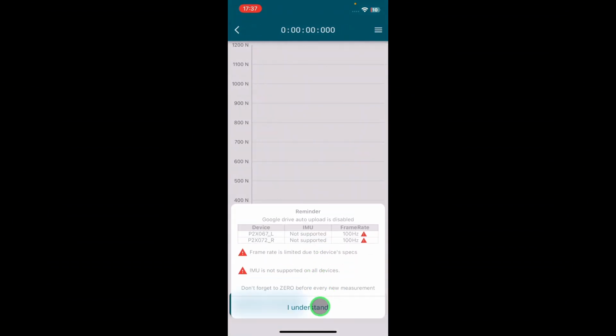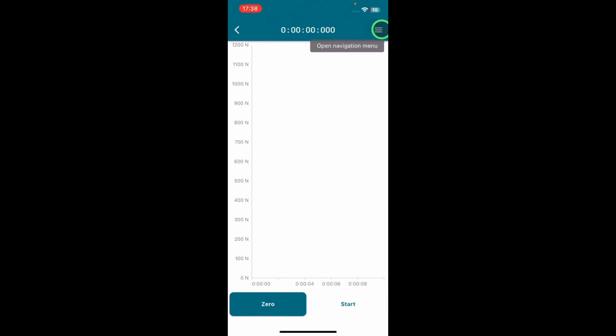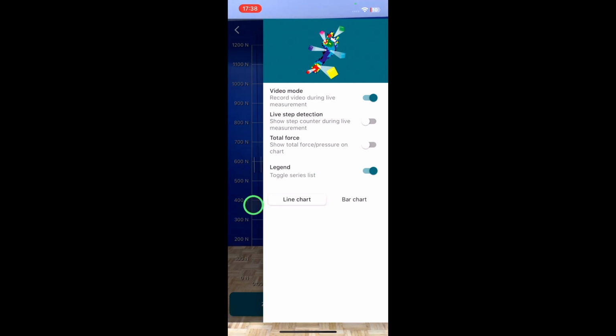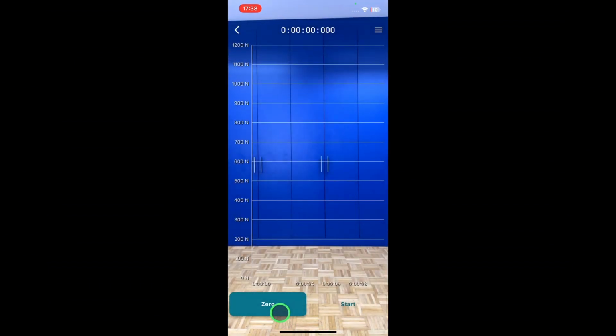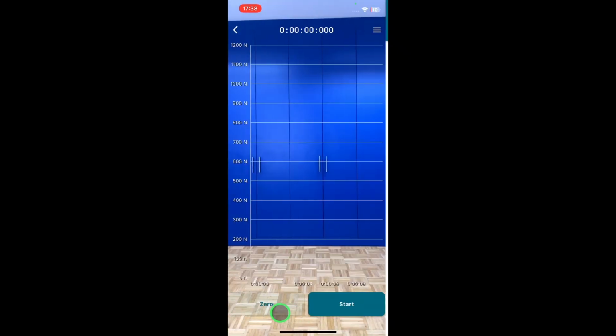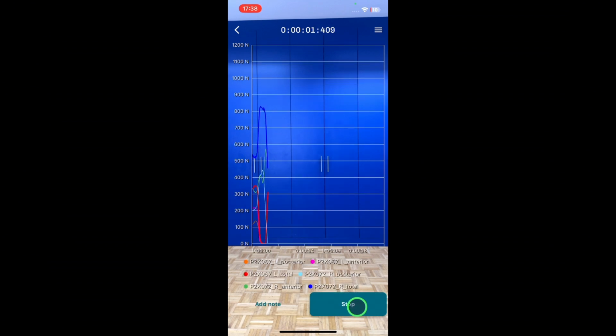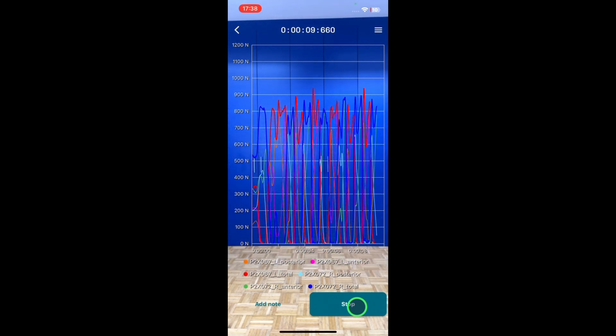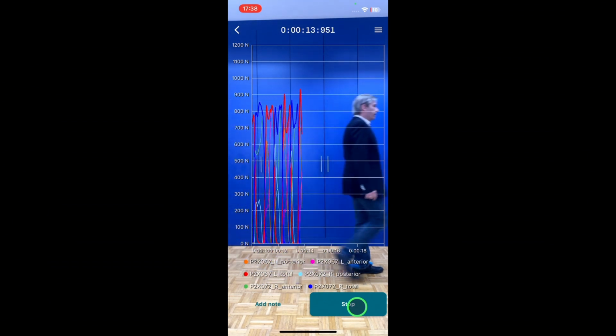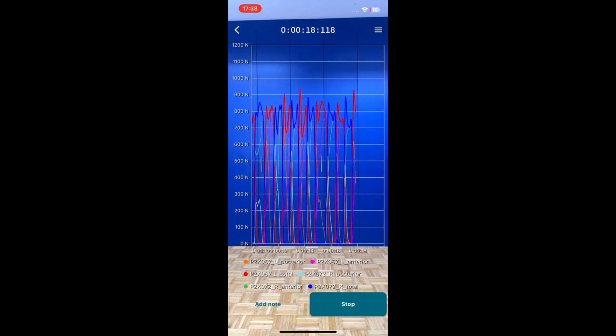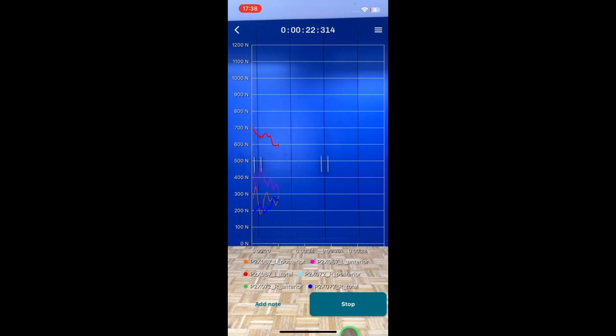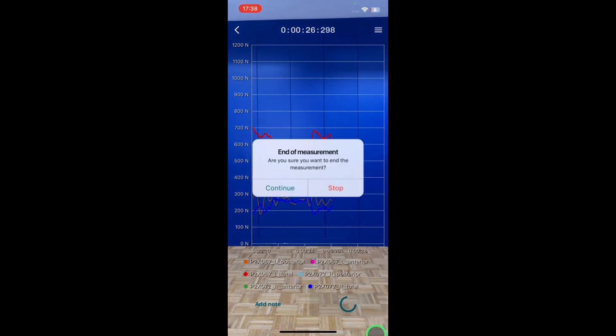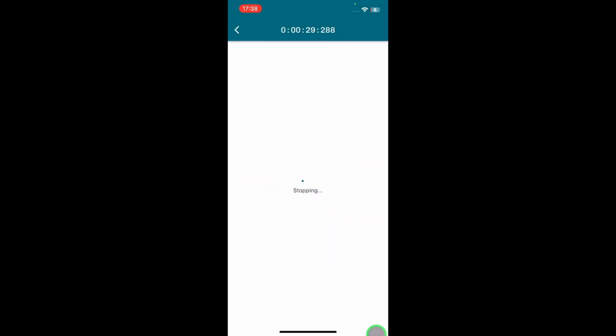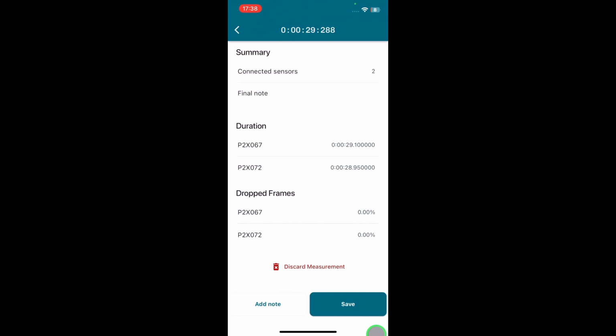Therefore, go to live chart. Again, you see the connected sensors here, and you go to the menu over here and you select the mode for video recording. Then again, one can do a zero measurement for left and right, and one can start now the data acquisition, and it's now automatically recording the video during walking. And when one can stop now, just like on a regular measurement, the data acquisition, stop it again, data will be saved. You can add another note if you want.